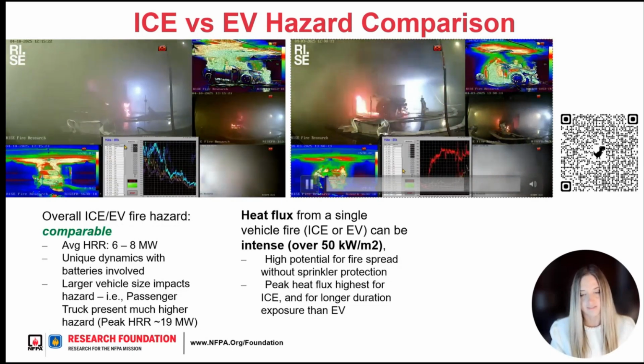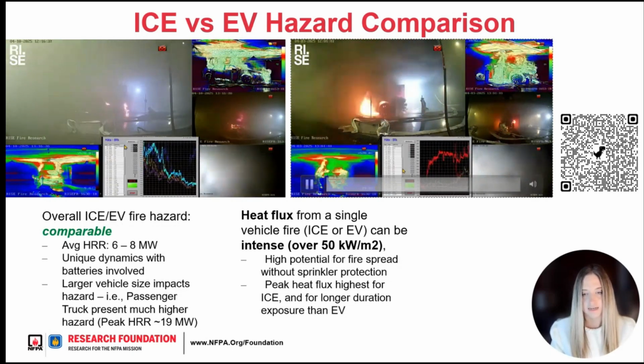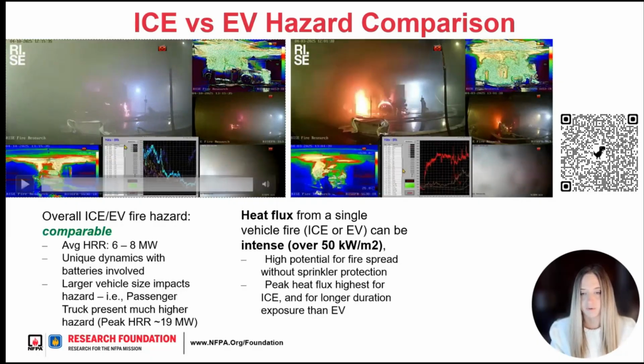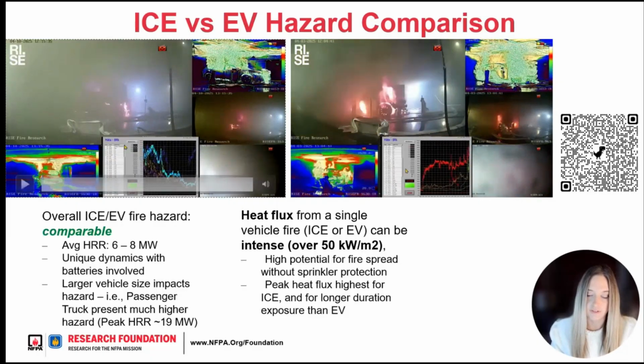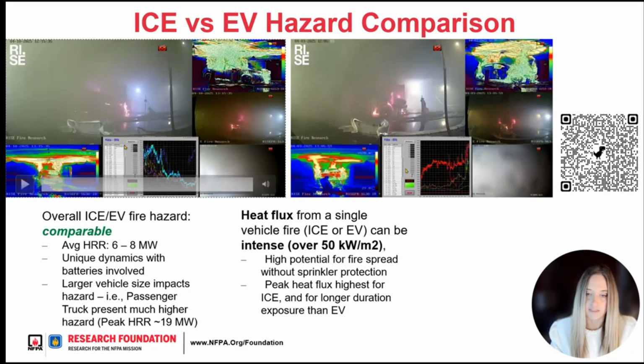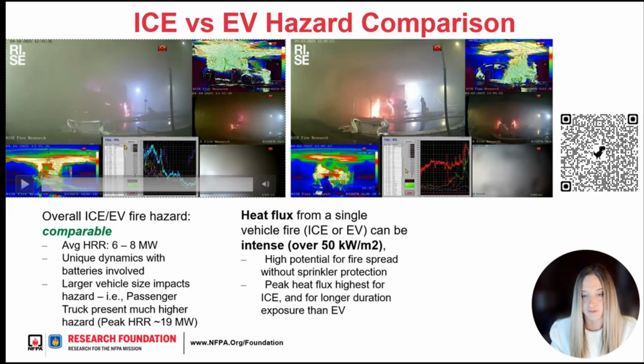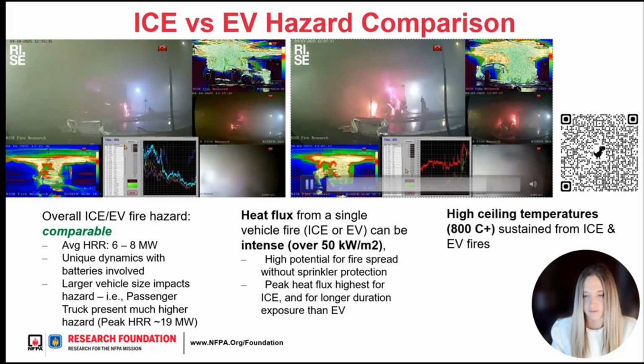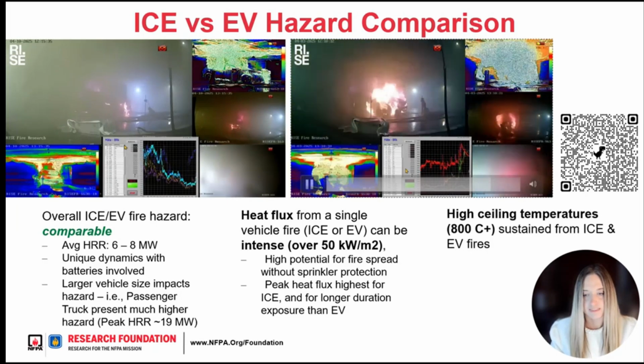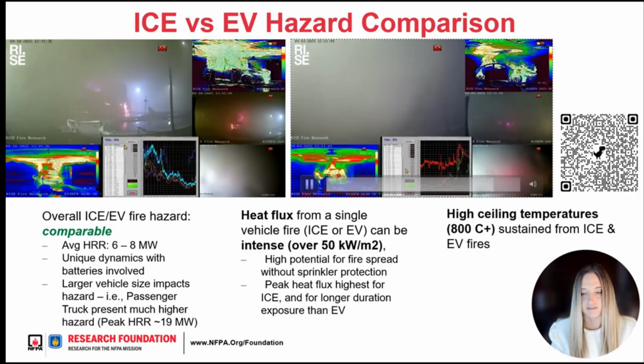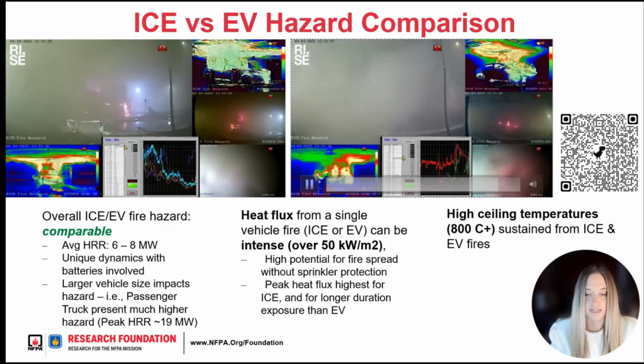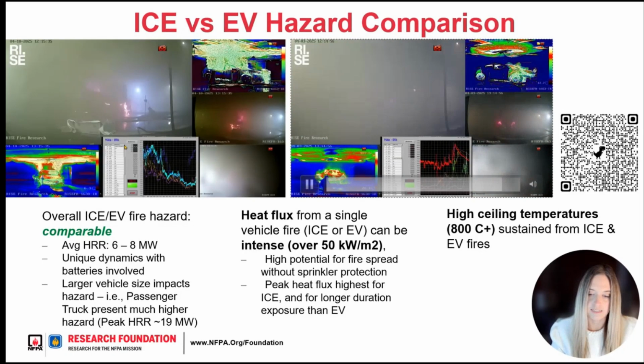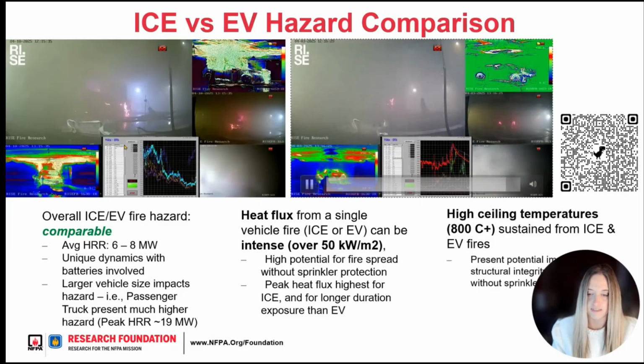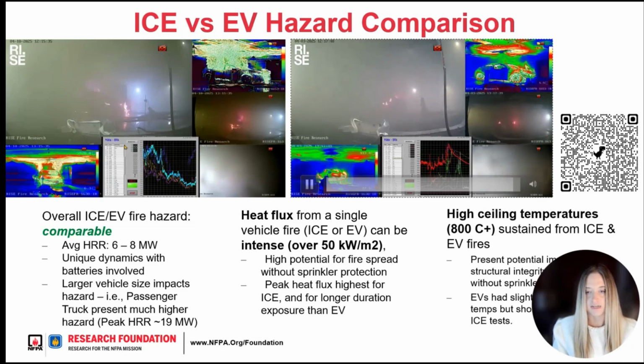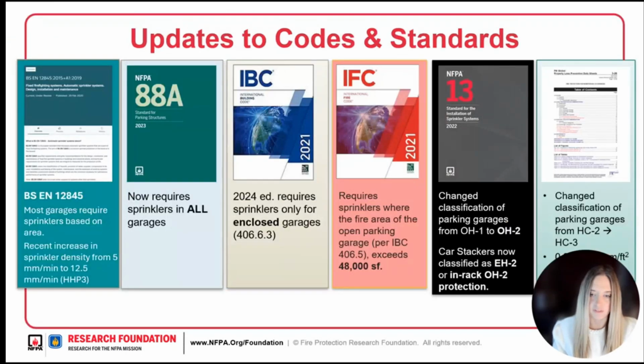We did find the heat flux to be a bit higher with the ICE test than the EV, but both had levels of heat flux that would make it likely for spread without sprinkler protection. The other important thing is the high ceiling temperatures from both vehicles were sustained around 800 degrees Celsius at the ceiling, which presents a potential structural integrity and spalling issue due to the long exposure.